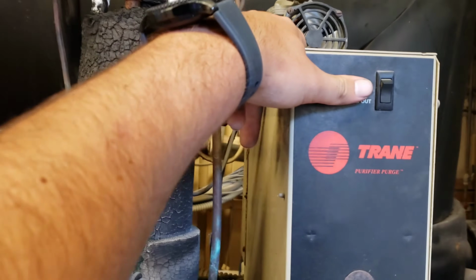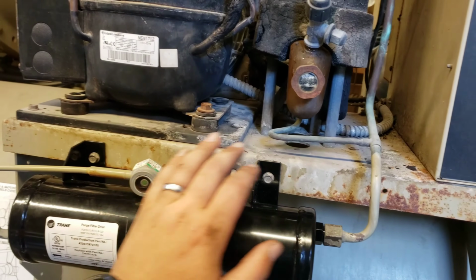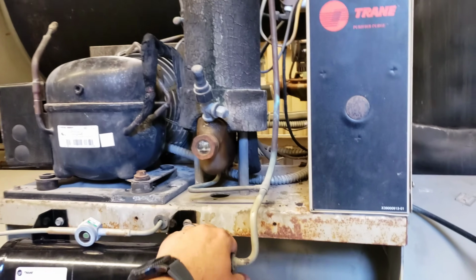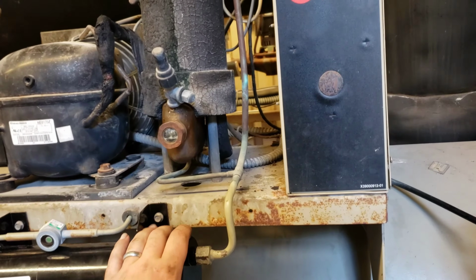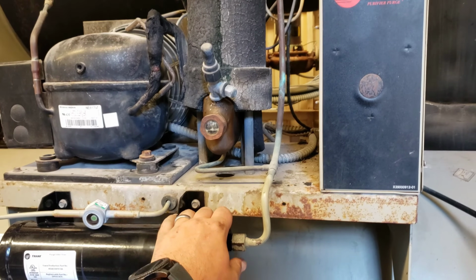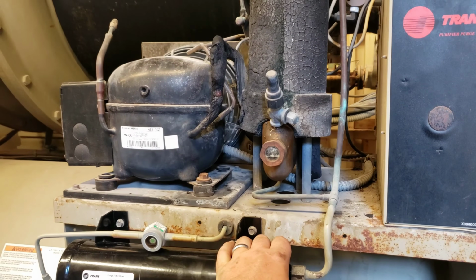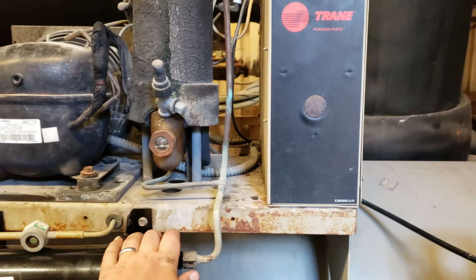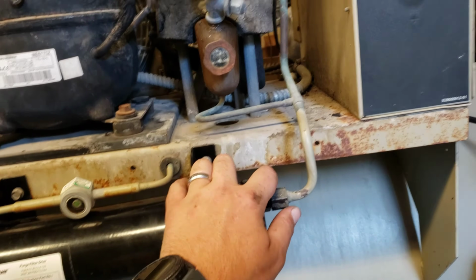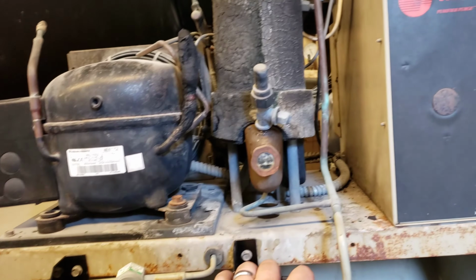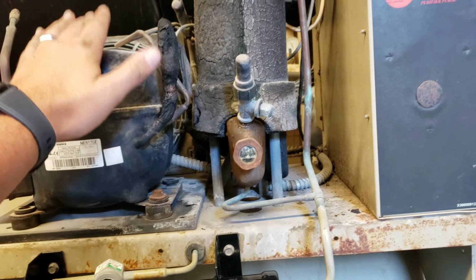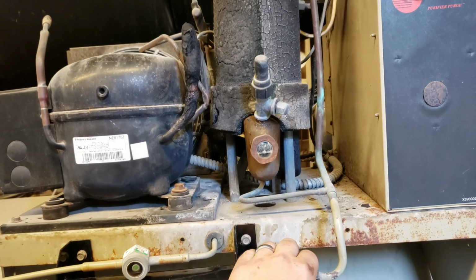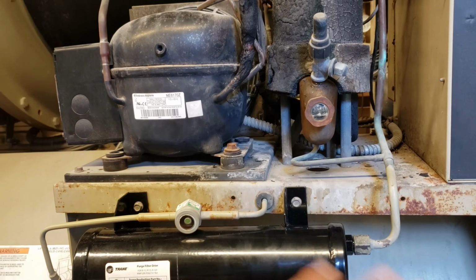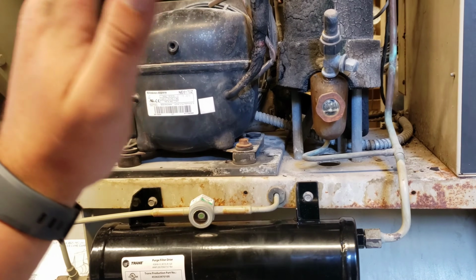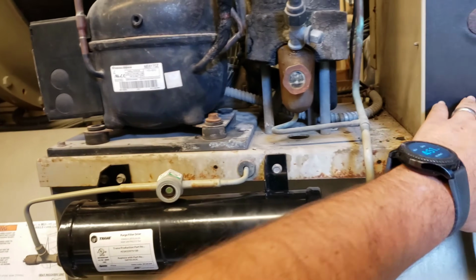As you just saw a second ago, the pump was running. It just satisfied, and it's cycling through now. I do have it off for the weekend, but I am going to leave the purge operating over the weekend so that it can try to help purge some of these non-condensables out. And what it looked like whoever had worked on it before had tried to do was run the system without going through the micro panel, and you can't do that on this particular setup. You bypass all the logics and the PIDs, and it doesn't know what to do when you do that, because they try to do it through the wiring.